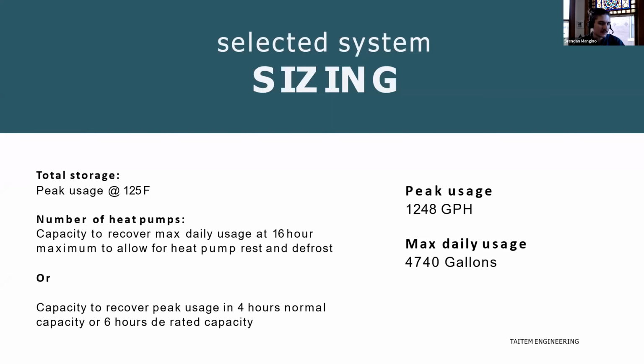We'll size the capacity to recover the peak usage in 4 hours under normal capacity, or 6 hours under derated capacity. And these Sanco systems at 15-degree ambient temperature start to derate from 4.5 kilowatts of effective generation to 3.5 kilowatts.